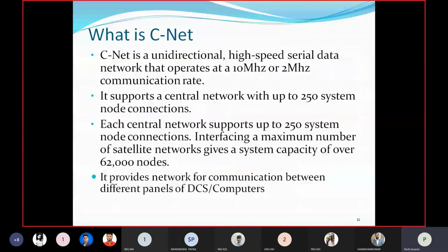So now, what is CNET? I already showed that photo of how the coaxial cable is connected, and each panel is connected with each other. I am going fast through the theory since I would like to show you more photos. CNET is a unidirectional high-speed serial data network that operates at a 10 megahertz or 2 megahertz communication rate. It supports a central network with up to 250 system connections. Around 250 panels can be connected in each network, and each network can again be connected with 250 others, so 62,000 node connections are possible. So now, this is only theory, but you can assume how big the control system is.